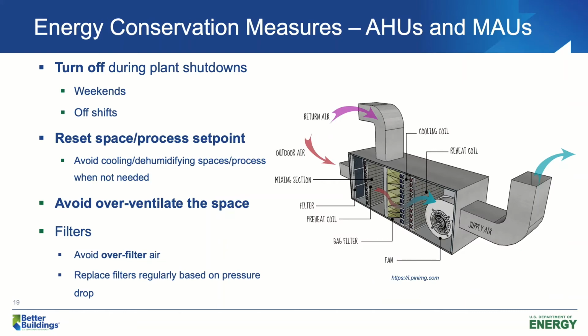Energy conservation measures for air handling units and makeup air units. Can we turn off our air handling units and makeup air units completely during plant shutdowns, for both weekend and off-shift shutdowns? If we cannot, can we reset the temperature and humidity set points a little bit higher? This way, our air handling units and makeup air units will not have to work as hard. Avoid over ventilation for spaces. We probably want to do some measurements and make sure that we are not over-ventilating our spaces. Of course, we do not want to under-ventilate our spaces because it might compromise the quality of our products and the health of our workers. But at the same time, we do not want to provide more than needed outdoor air because that means an energy penalty.